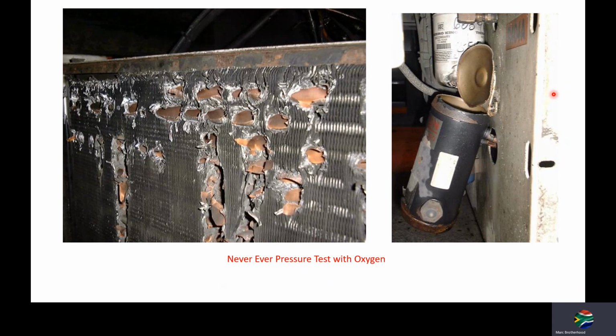Here we see we must never ever pressure test with oxygen. Oxygen is required for combustion, and under high pressure in contact with oil, the diesel effect is deadly. So pretty much what's happened here, there's refrigerant oil within the pipework. The oxygen has come out under very high pressure, and that pressure has acted like a piston effect, and under high compression mixing with the oil, you reach flash point and the oxygen combusts, and it blew up this evaporator, throwing all the shrapnel possibly into the technician's face.